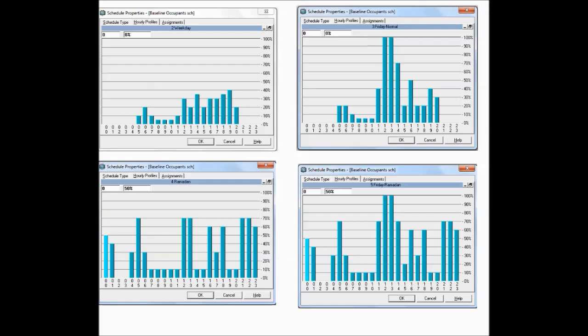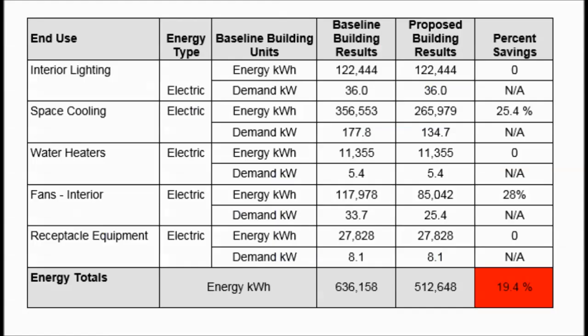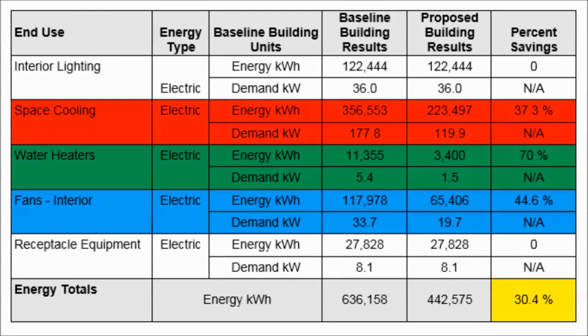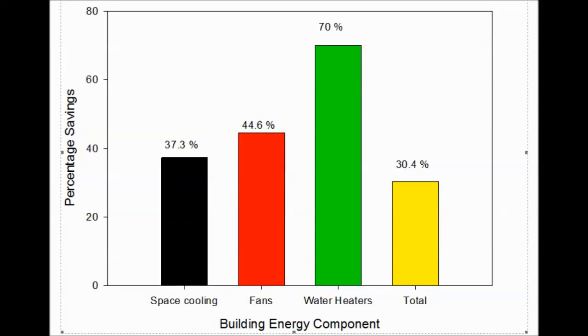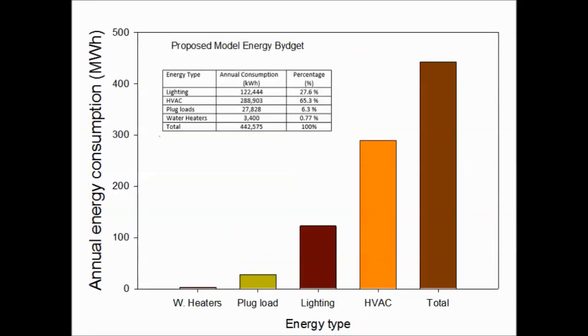The results show that the proposed smart system can lower the total annual energy of the building by almost 20%. The final results showed a great improvement in the building's total annual energy demand. The 6 strategies discussed in this work were able to reduce the total annual energy demand by almost 30%. The HVAC system annual load, which includes space cooling and fans, was reduced by almost 40%, while the water heater's load was reduced by 70%. The lighting load and the plug loads were unchanged, but their share in the new energy budget increased as the other components' share decreased.